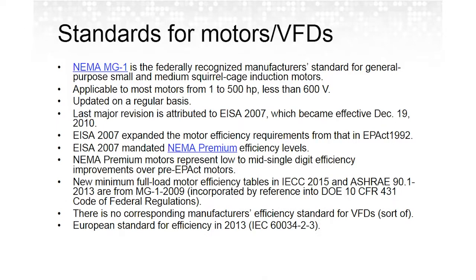However, this hasn't been adopted yet by the federal government, incorporated into the U.S. code, and it's expected that you would most likely see a standard either coming out of IEEE or NEMA as far as an efficiency standard. It should be noted that in the European Union there is an efficiency standard that was created in 2013, IEC 60034-2-3.